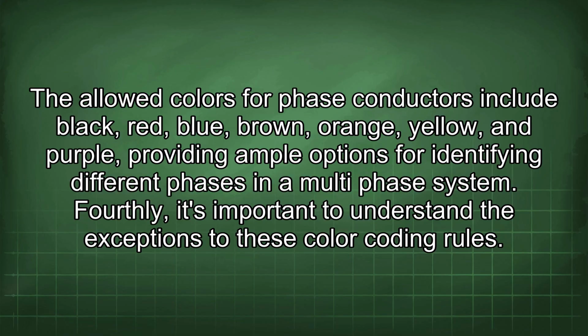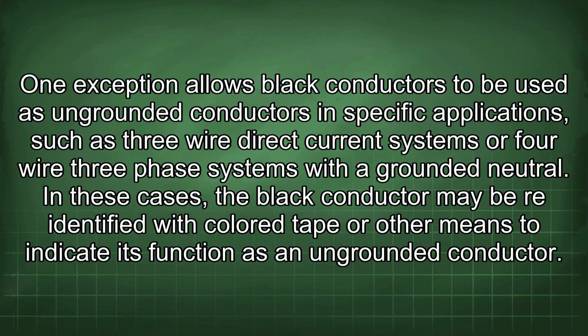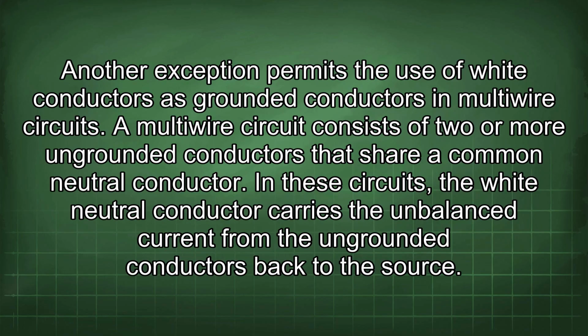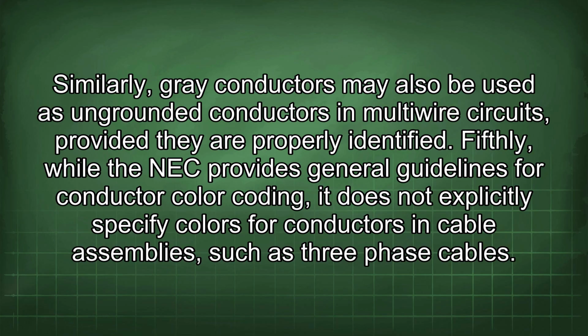Fourthly, it's important to understand the exceptions to these color coding rules. One exception allows black conductors to be used as ungrounded conductors in specific applications, such as 3-wire direct current systems or 4-wire 3-phase systems with a grounded neutral. In these cases, the black conductor may be re-identified with colored tape or other means to indicate its function as an ungrounded conductor. Another exception permits the use of white conductors as grounded conductors in multi-wire circuits. A multi-wire circuit consists of 2 or more ungrounded conductors that share a common neutral conductor. In these circuits, the white neutral conductor carries the unbalanced current from the ungrounded conductors back to the source. Similarly, gray conductors may also be used as ungrounded conductors in multi-wire circuits, provided they are properly identified.